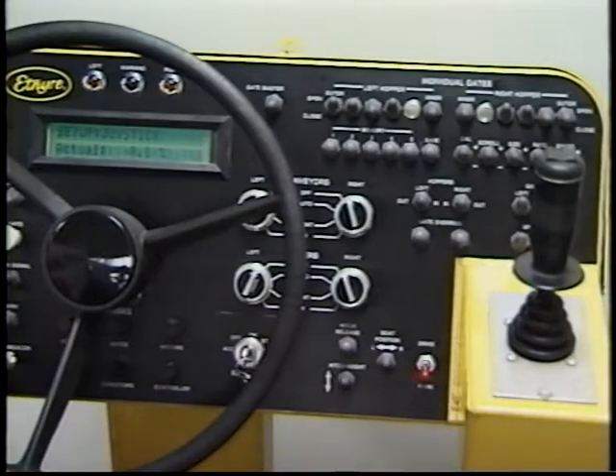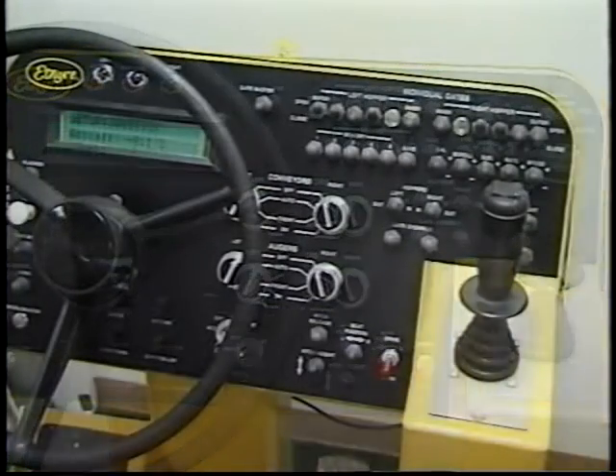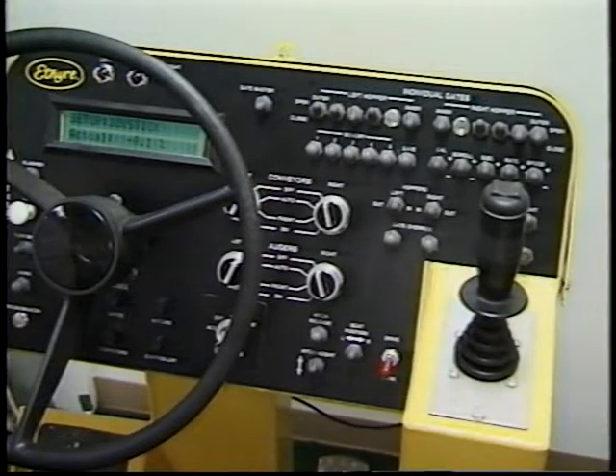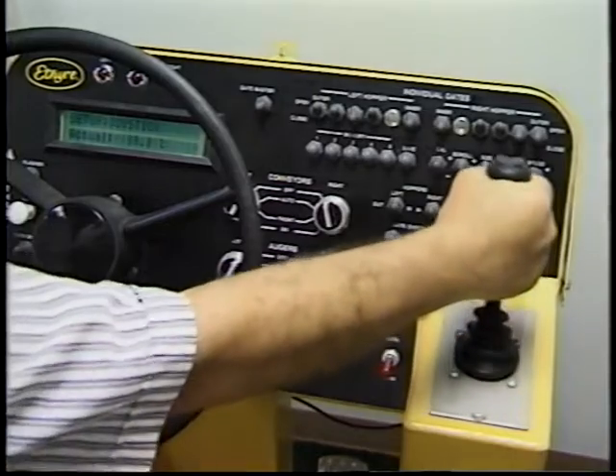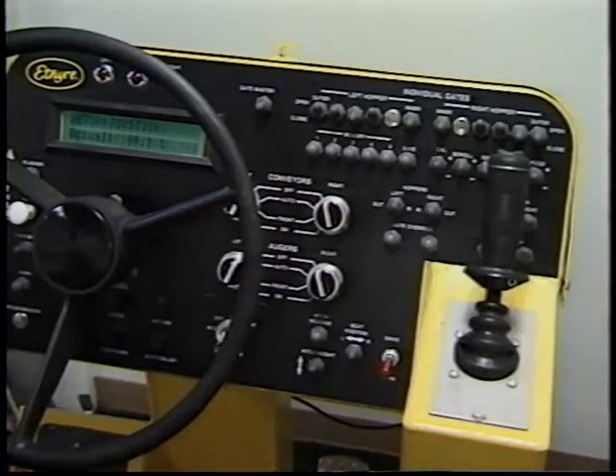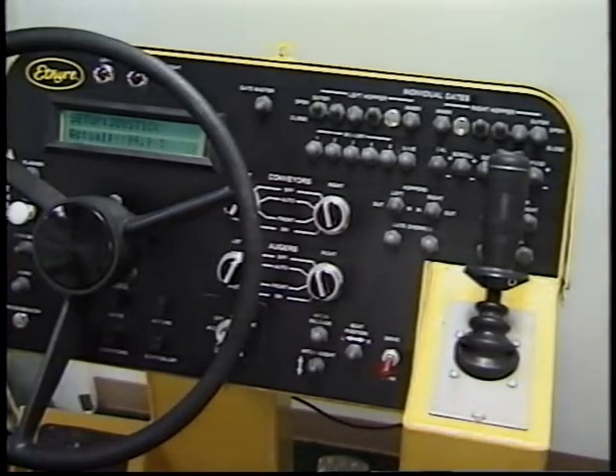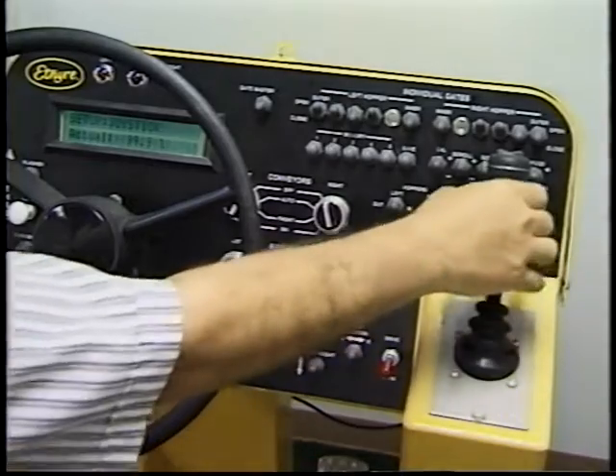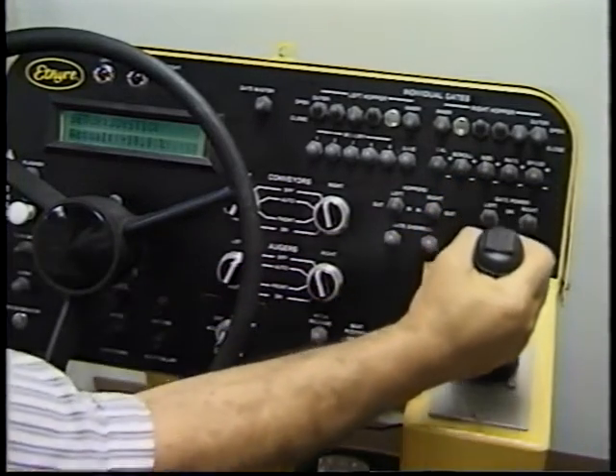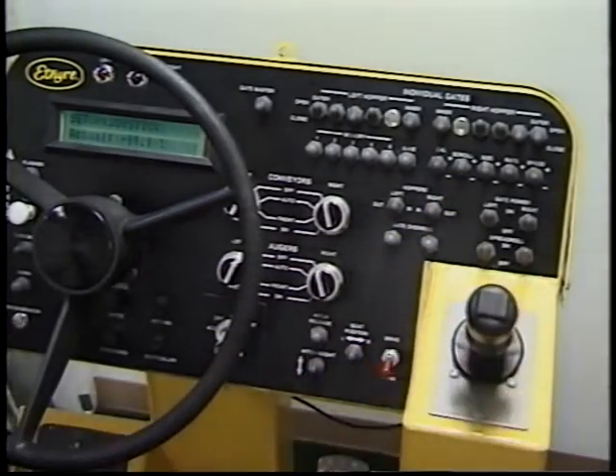This screen is the entry screen for calibrating the joystick. It should say 0% with the stick in neutral. If the stick is pushed full forward, the reading should change to 100%. And if it is pulled fully back into reverse, the reading should change to -100%.